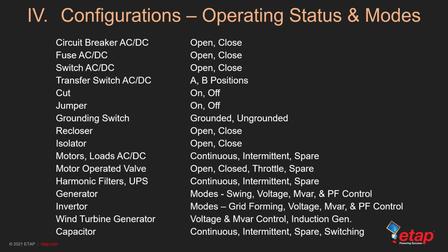Configuration is the status of the system and the modes of operation of its elements. For example, circuit breakers can be open or closed, switching devices can be open or closed, and they can be in different positions if there's a transfer switch, cut jumpers, or reclosers. Motors can be continuously operating, intermittent, or spare, and motor-operated valves can be open, closed, or throttled. UPS units work the same way. Generators can have modes of operation like swing, voltage control, megavar, and power factor control. Inverters can have modes from grid-forming to voltage, megavar, and power factor control. The same applies to WTGs, and capacitors can be continuous or switching, and so on.